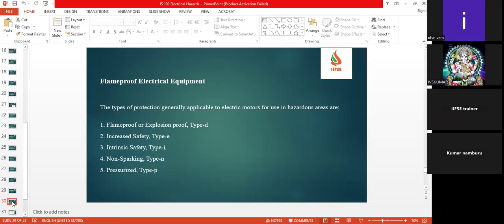Excuse me. There are different types of protection. Generally, it is applicable in electric motors for use in hazardous areas. So flame proof or explosion proof, these are type D; increased safety, this is type E; intrinsic safety, type I; non-sparking, type N; and also pressurized, type P. These are the different types of flame proof electrical equipment.